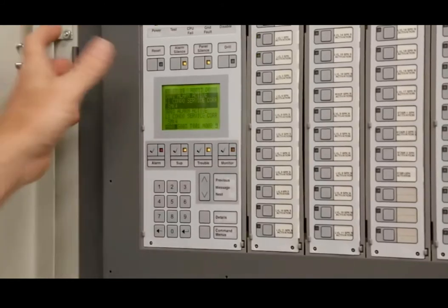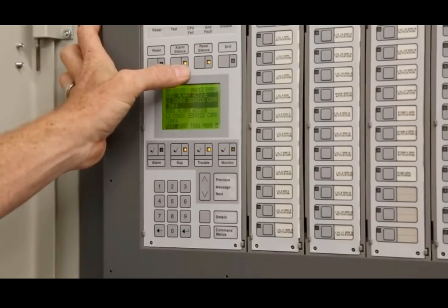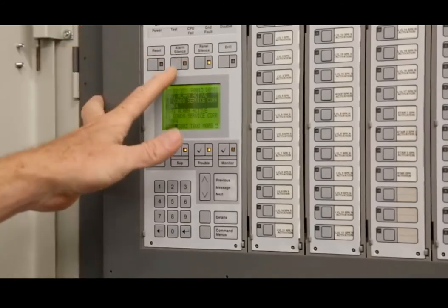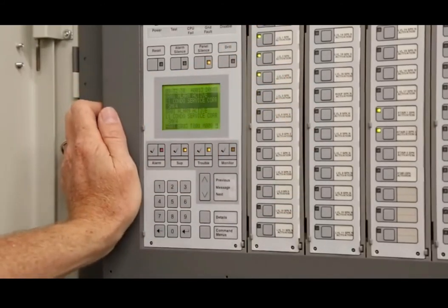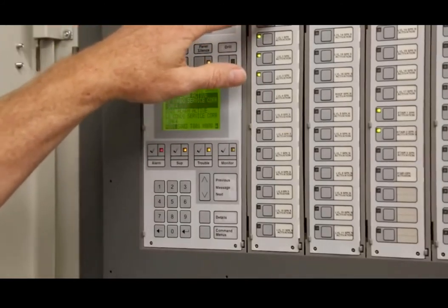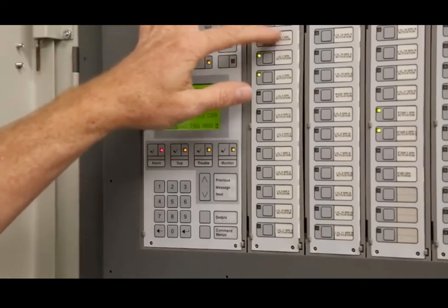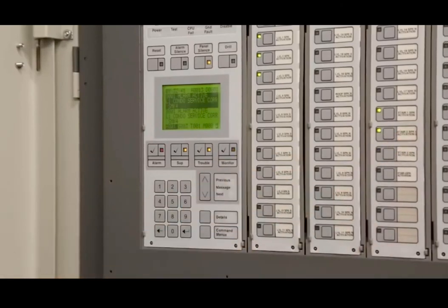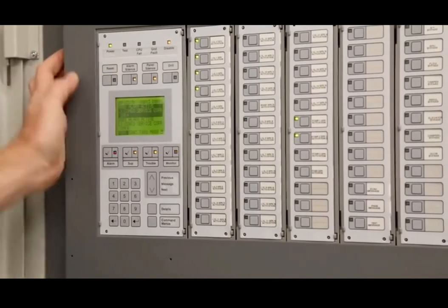So if you panic and hit it twice, just keep in mind, if the light's lit, it's activated. Okay? So right now it's silenced. If the light is not lit, obviously it's going off. And you can see what floors right now we picked. So for instance, right now, it's a low rise portion. We had the 0 level going off, 1, 2, and 3 going off, and then we get the staircase on this side going off. Okay? So again, you can just silence it right there.